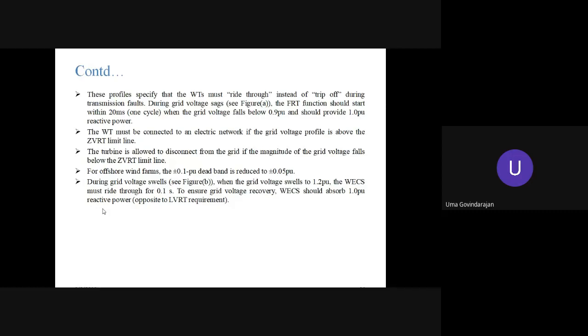To ensure grid voltage recovery, the wind energy conversion system should absorb 1 per unit reactive power. This is in contrast to the LVRT requirement. In the case of LVRT, when the voltage falls below 0.9 per unit, the wind energy conversion system should provide 1 per unit reactive power. Whereas in the case of HVRT, high voltage ride-through, it should absorb 1 per unit reactive power. So during this fault condition, it is very, very essential that the wind generators along with the converter provide or absorb the reactive power, so that the generators will stay connected, or ride through the faults. That is very important.